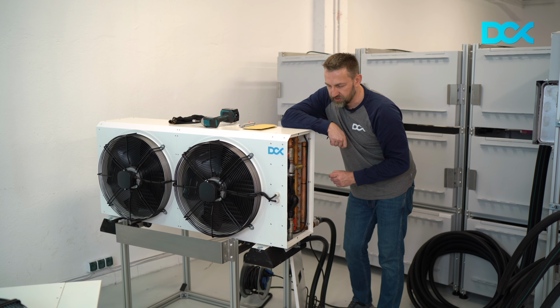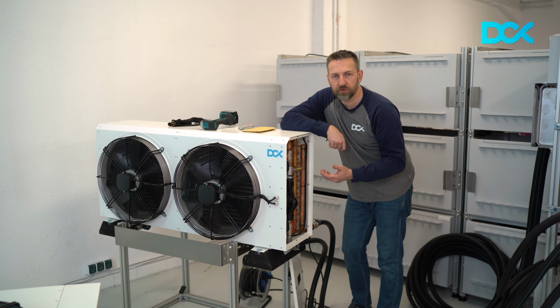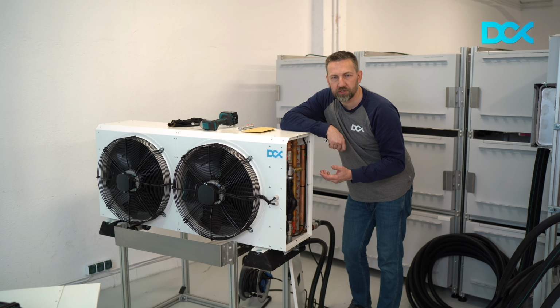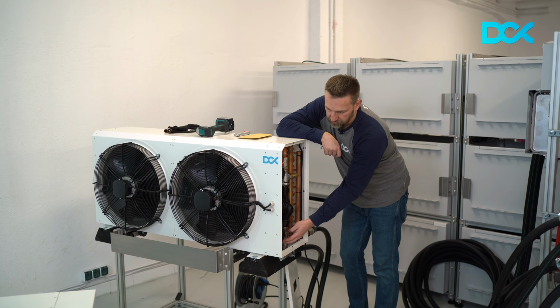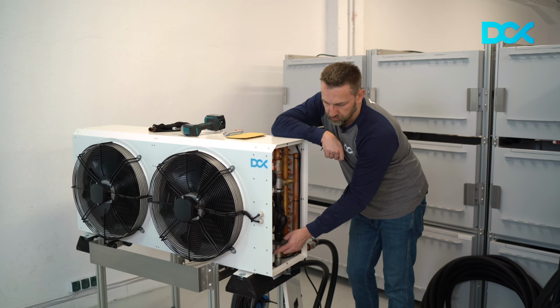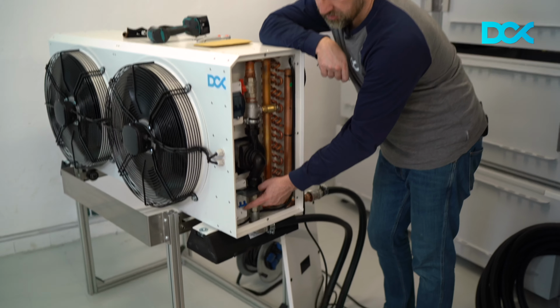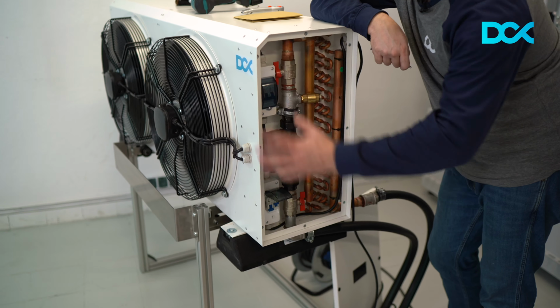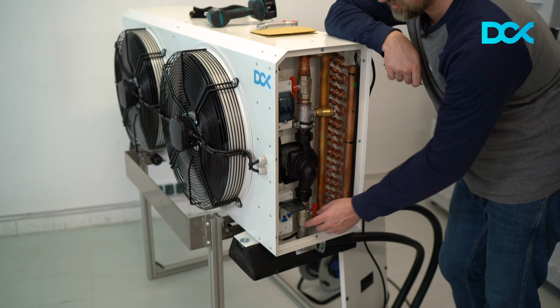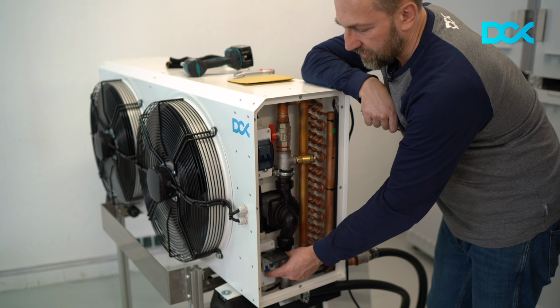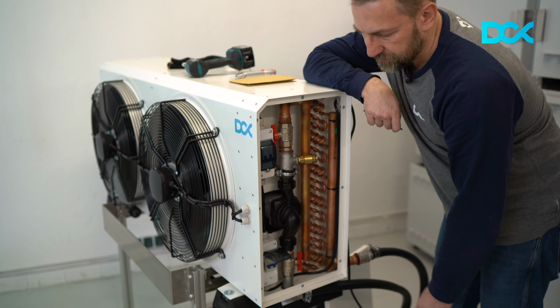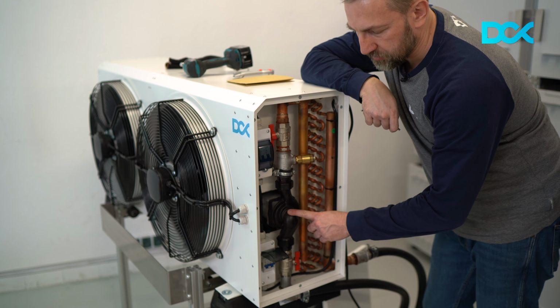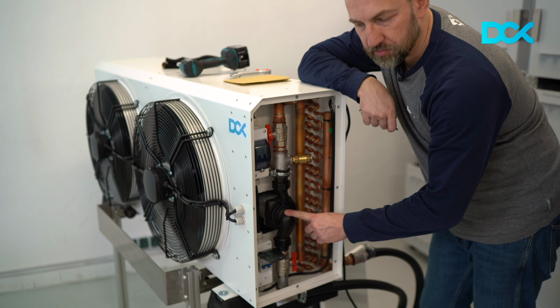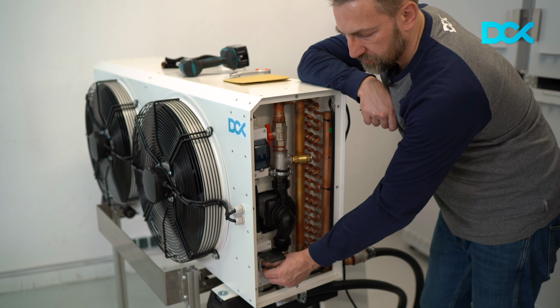Now let's start from the electrical side, and that's the final process before starting the operation. So you have two switchgear boxes, one on the bottom, one on the top. The one on the bottom has two breakers: one general on the right, which works for the whole system and protects the whole component, and the second one is powering the pump. So you can observe and feel that the pump is starting.